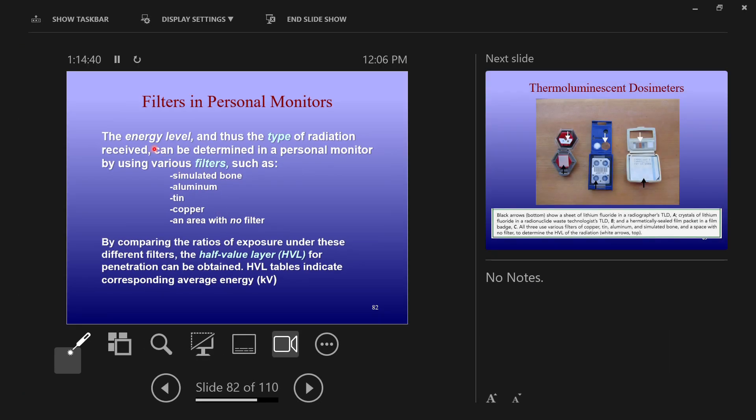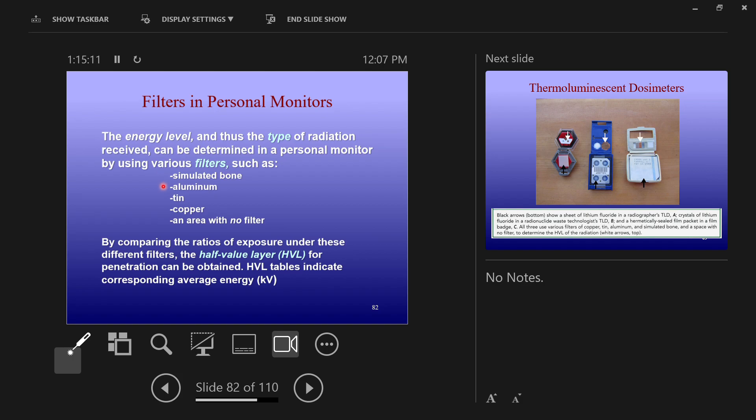All of these use filters. They'll put little tiny circles or squares of different materials, and then they can tell behind the simulated bone, how much radiation did the badge receive? Behind the aluminum, how much did the badge receive? And they can use these different materials to infer how much exposure each part of your body received. Simulated bone, aluminum, tin, copper, no filter at all. They use these different materials to infer dose to different parts of your body.